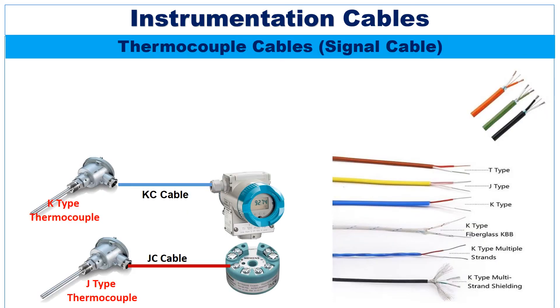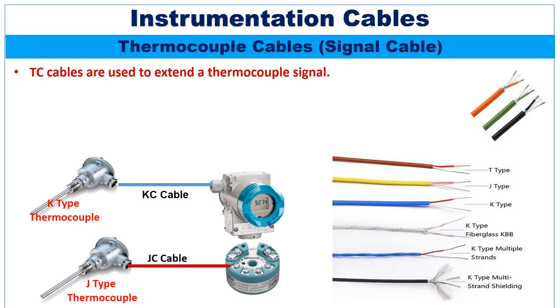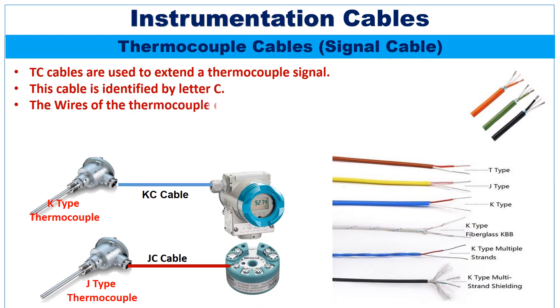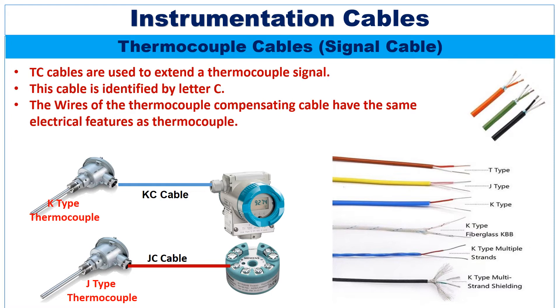Thermocouple compensating cables are also a type of signal cable. The thermocouple compensating cable is used to extend the thermocouple signal from the thermocouple to the transmitter. This cable is identified by the letter C — for example, the compensating cable for a K-type thermocouple will be a KC cable. The wires of thermocouple compensating cable have the same electrical features as the thermocouple, but do not use the same materials as the dissimilar wires of thermocouples.